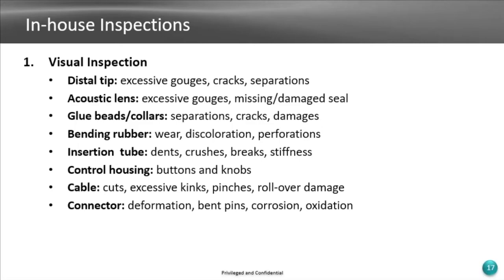But it gets better, because then they're going to unplug that probe and plug another probe into that damaged port, and it's not going to fit right, so they'll jam that probe in too. Now you've damaged another probe, and it goes on and on. So you want to constantly inspect the pins on these probes and the ports on the machine to make sure none are damaged, because that problem will only grow.